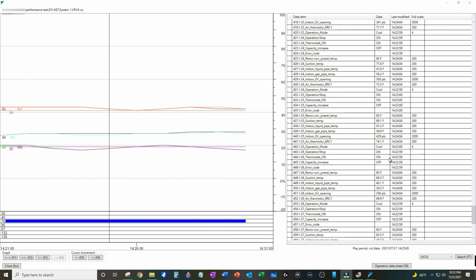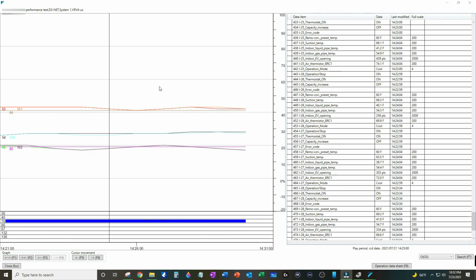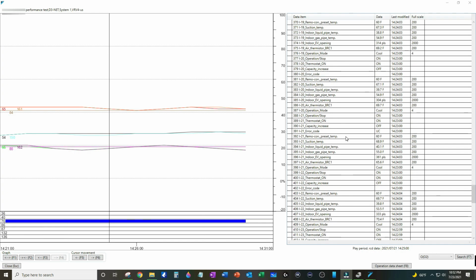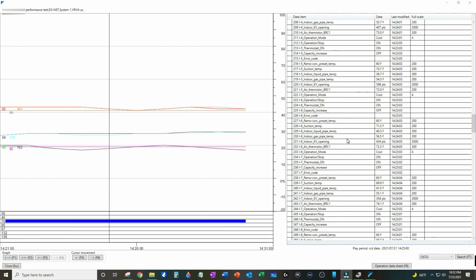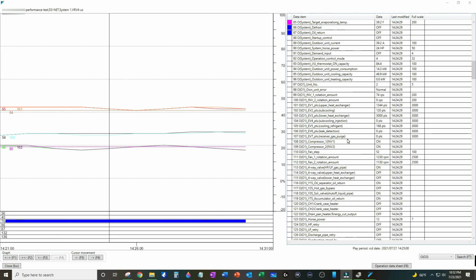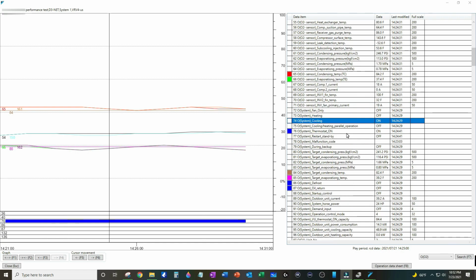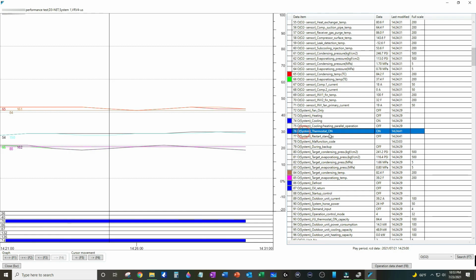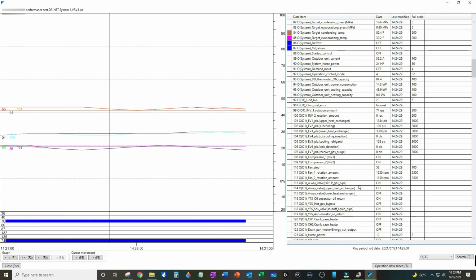I'm sure you're also wondering what this big graph is for. By default, every time you display a new data window, the program will populate certain data points. I like to personally select my own during the startups based on what I'm checking for. For example, I always like to graph the thermo on status of the system so I know when the outdoor has a demand or call to operate. It makes it very easy to see because the blue bar will populate near the bottom, which is easy to see while I'm scrolling around looking at other stuff.